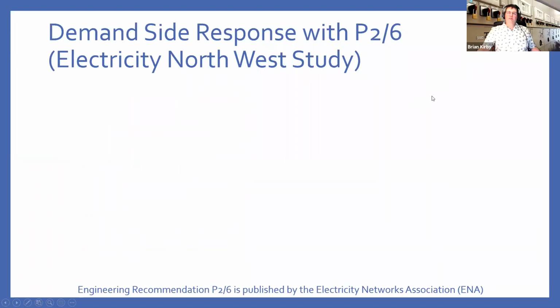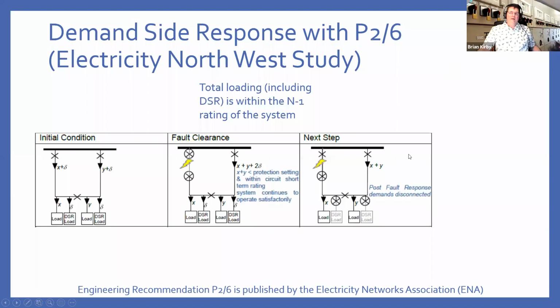Demand side response. Electricity Northwest did a study on this. What you have on your system is your permanent load and your DSR load, which is your delta. And under normal conditions, you have two feeders supplying them. You get a fault on one of your feeders, but your load is less than the protection setting for this feeder, so your system stays healthy, but your demand side load is switched off because you want to maintain your margin.